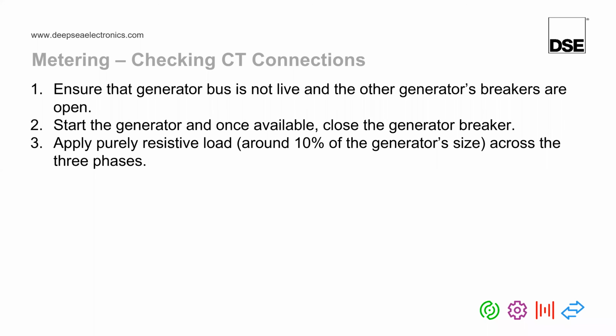Now, ideally, this purely resistive load would come from a load bank. And ideally, the load bank would be a 3-phase load bank as well. Now, the load bank itself does not need to be big. It can be quite a small load bank because in this test, we're not actually load testing the generator or testing its load acceptance or rejection capabilities. We're just making sure that it can measure the kilowatts and current and power correctly. Now, I do appreciate that in a lot of cases, getting a load bank to site, or even during testing and manufacturing, can sometimes be difficult.